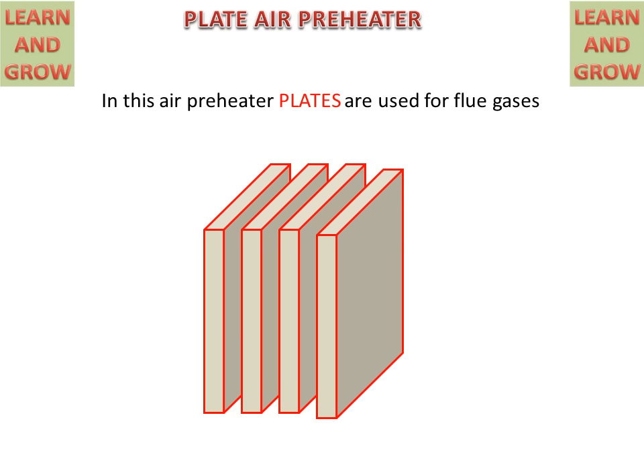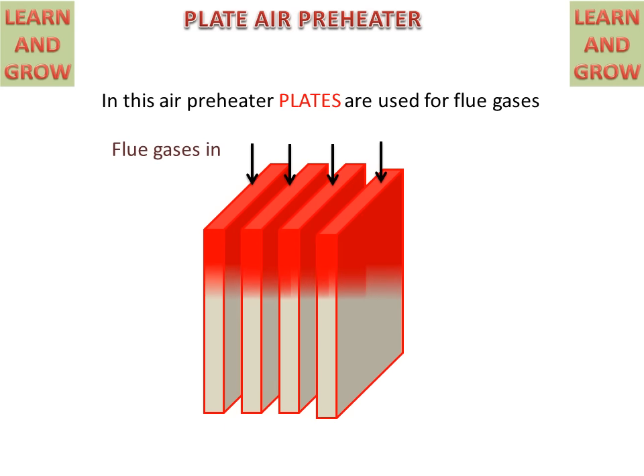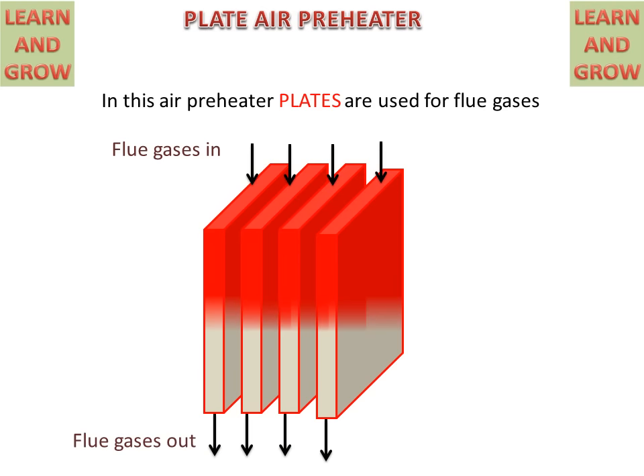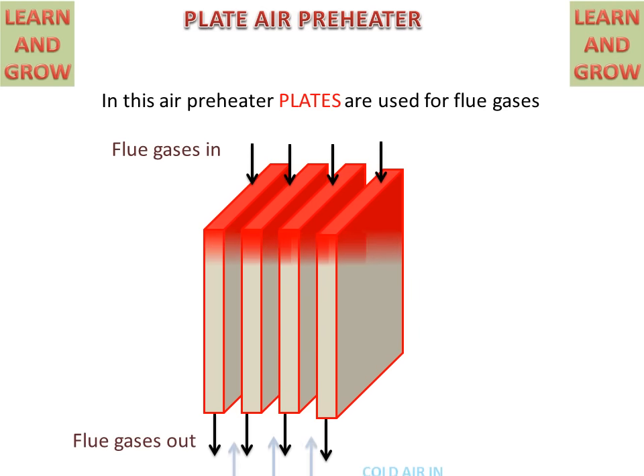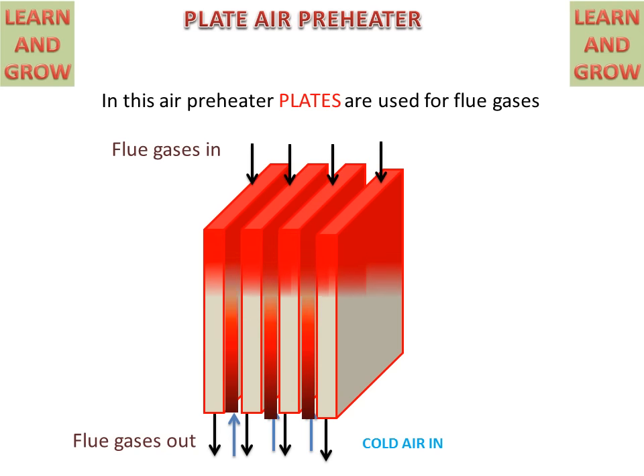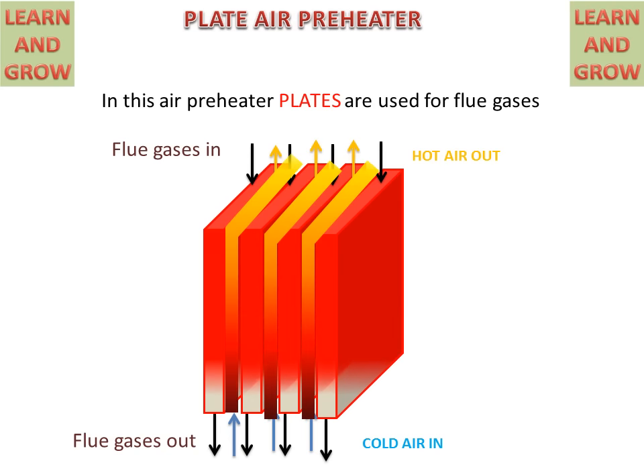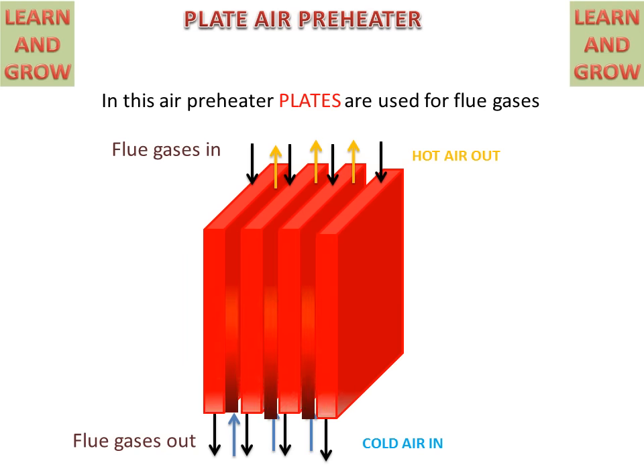In plate type air pre-heater, plates are used for flowing flue gases and air. There are closely spaced plates. Flue gases will be entered in these plates, the plates will get heat from the flue gases and go outside. Cold air will be entered from the space between the plates and hot air we will get on the other side. This is the basic principle of plate type air pre-heater.